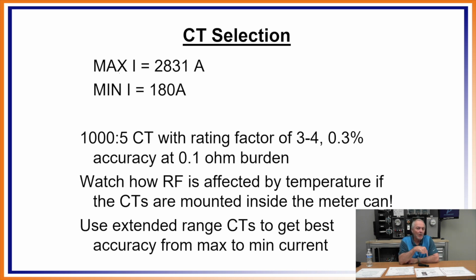But we said this earlier, watch your temperature, okay? This is a great example that Steve gave right here, if you think about it. So 2831, if I had a 1,000 to 5 CT and I had a rating factor of 3, that's 3,000, right? What if the temperature influenced it? I could get down below that pretty quickly, couldn't I? So what I would probably do in a high temperature situation, I might go with a rating factor of 4 to cover myself, okay? All right.